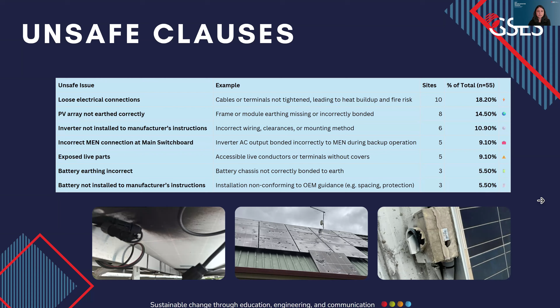Thanks, Fernanda. During our inspections, we have found that many installers are not earthing the inverter frame or the battery frame correctly or at all. Initial discussions with the Electrical Safety Office and other key industry stakeholders considered deeming this issue as unsafe. However, since there is an earth connection through the AC earth, it was only considered as substandard. The frequency of an issue resulting from this improper earthing would be very low, but the consequence could be very high.